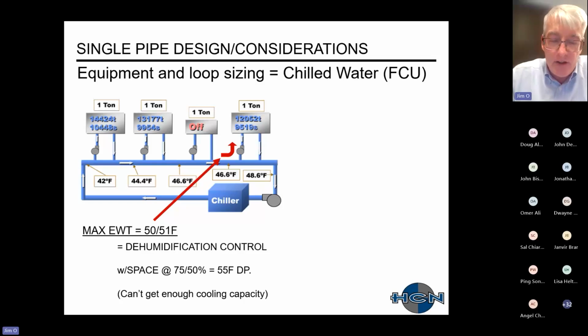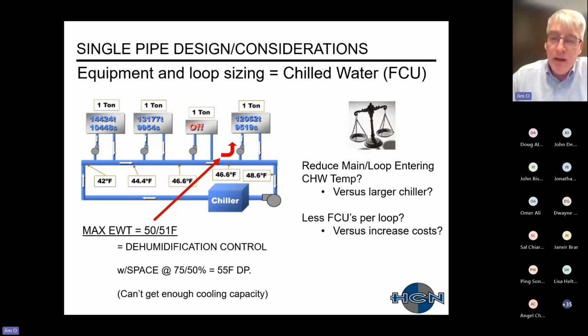Just look at it: a typical space is at 75 degrees and 50% relative humidity. That 50% turns into a dew point temperature of 55. So basically you're looking at the difference, the delta T, between that water temperature of 50, 51, 52, et cetera, and a dew point temperature of 55. What will happen is if that water is too warm, you can't get enough cooling capacity out of your fan coil.